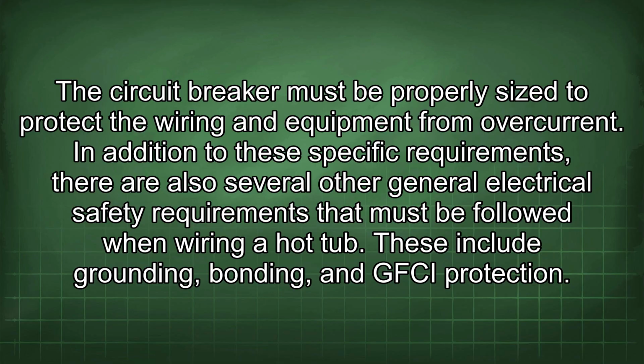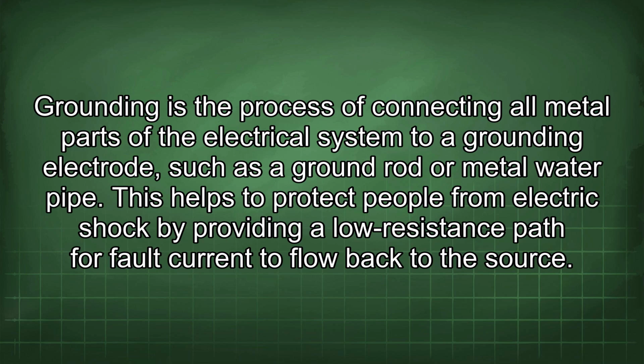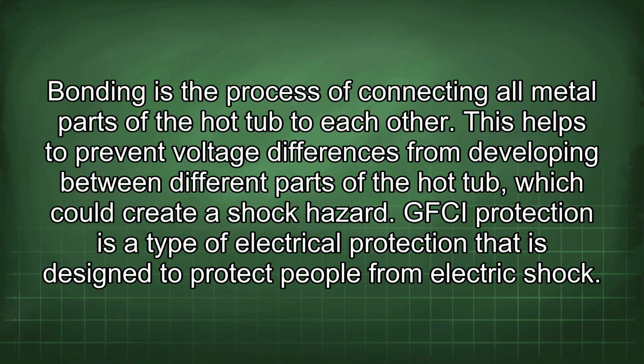In addition to these specific requirements, there are also several other general electrical safety requirements that must be followed when wiring a hot tub. These include grounding, bonding, and GFCI protection. Grounding is the process of connecting all metal parts of the electrical system to a grounding electrode, such as a ground rod or metal water pipe. This helps to protect people from electric shock by providing a low resistance path for fault current to flow back to the source. Bonding is the process of connecting all metal parts of the hot tub to each other.